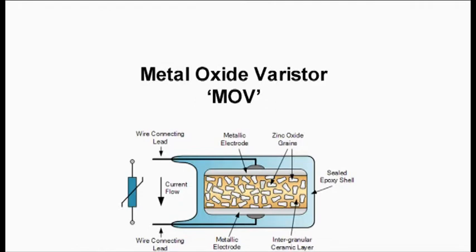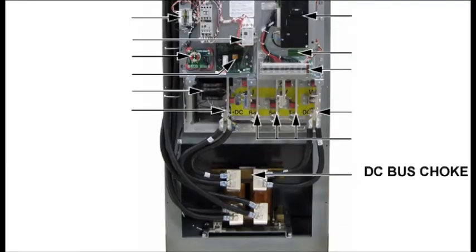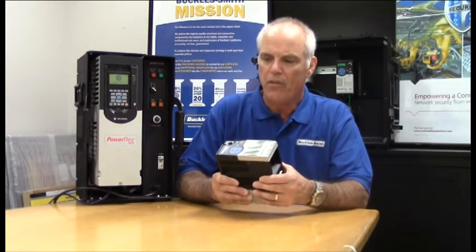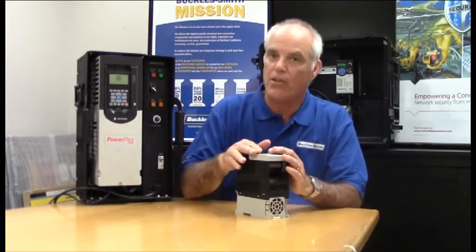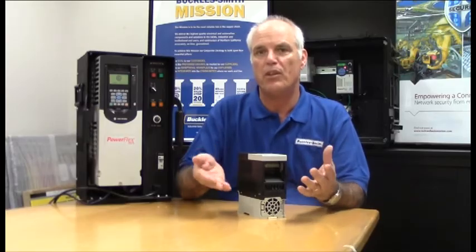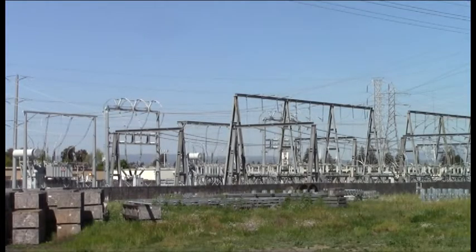Modern VFDs have some form of input protection in the form of metal oxide varistors, or MOVs. These devices can react to voltage surges and protect circuits downstream. They can absorb some transients, but they become less effective each time they take a hit. Also, many of our drives have a DC bus choke. That helps protect the main capacitors in the drive from spikes and sags. Both of these features are helpful, but as drives become more microprocessor-based and smaller in size, it's increasingly difficult to build in protective devices to handle transients in high-voltage three-phase systems.